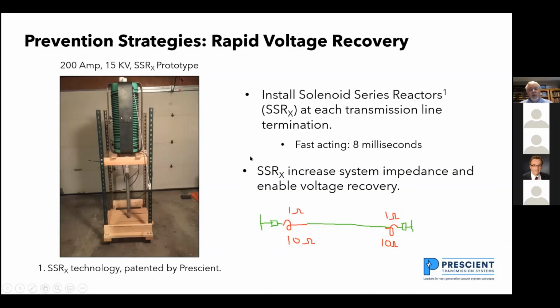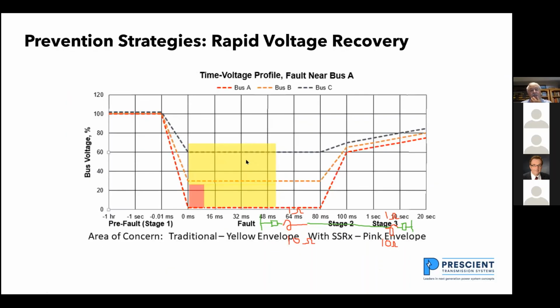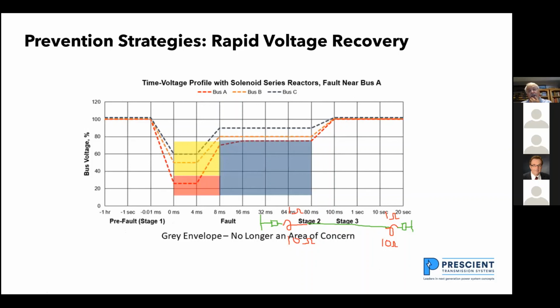And when this changes from 1 to 10 ohms, what happens is I change the circuit impedance so that now when a fault occurs, the voltage at the fault is 0. And when I put the solenoid series reactor in, that 1 ohm is going to stop me from going from 0 voltage to some other voltage, like maybe this is showing 25% voltage on the bus closest to the fault. And when it changes position, it pulls the voltage up to 70%.